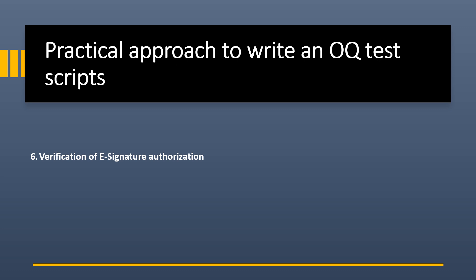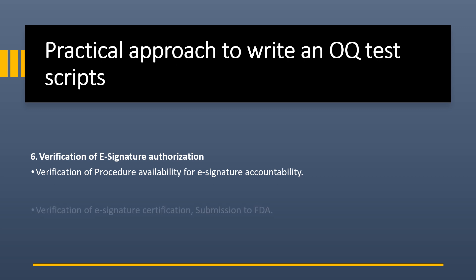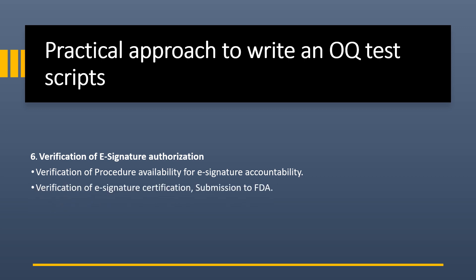Sixth is verification of electronic signature authorization. This includes: verification of procedure availability for electronic signature accountability; verification that the electronic signature certification has been submitted to the FDA stating the intent of using electronic signatures; and verification that electronic signatures appear in electronic reports showing who performed, reviewed, and approved the data.